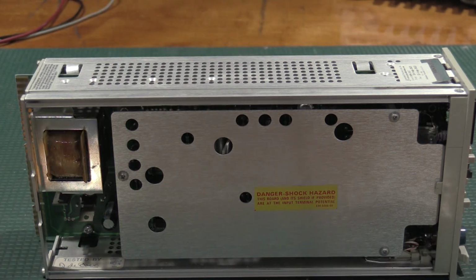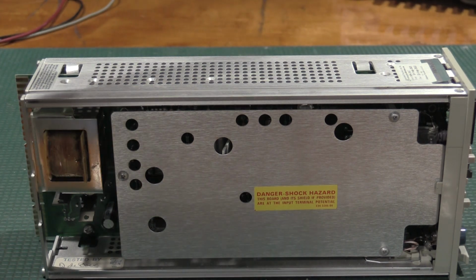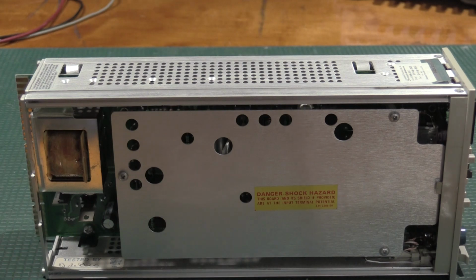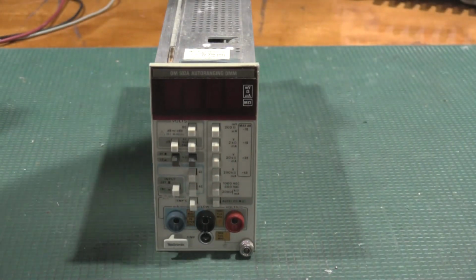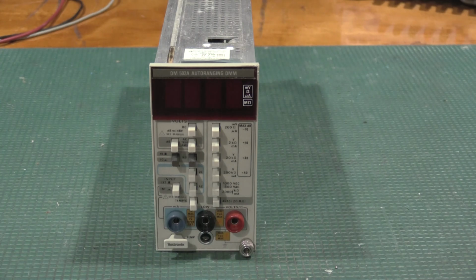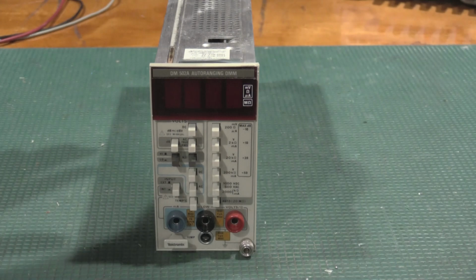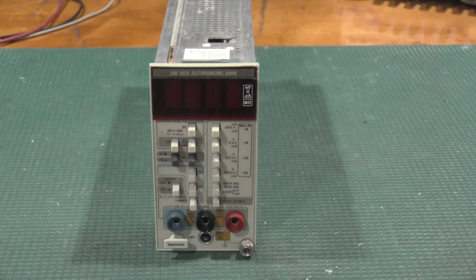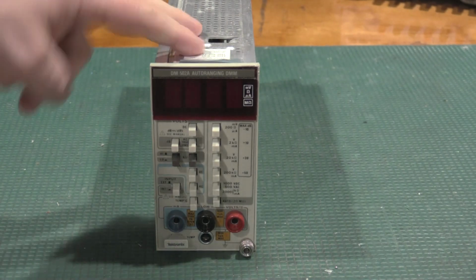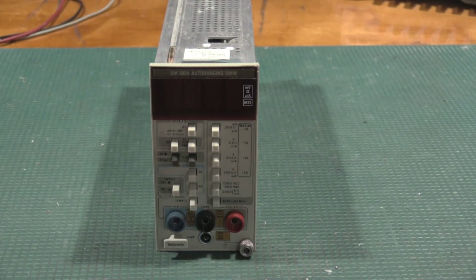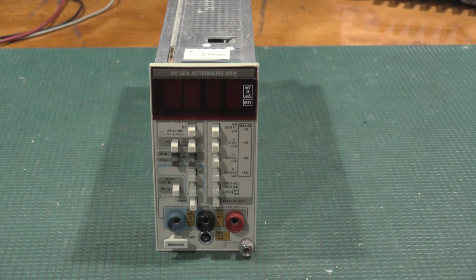I'm not going to show the alignment process in this video. I do have a prior video where I go through the alignment process of one of these in detail. These are relatively easy to align. The real tricky part with aligning meters in general is hitting the high ranges. So I have to put in 910 volts to align this at its highest range, because it does have a 1,000 volt input, so they align it at about 910 if I remember the spec right. The other problem is the AC alignment: you have to get very high voltage AC into one of these things, and that's usually where the alignment kind of falls off.